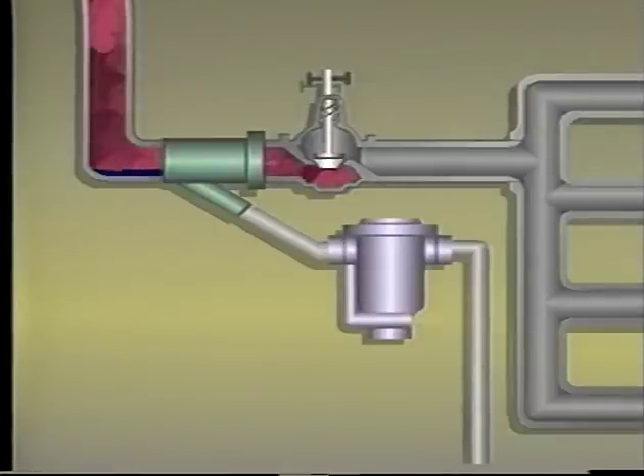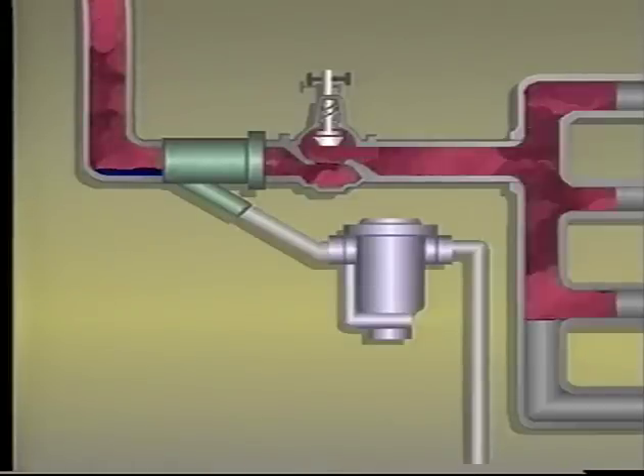The installation of a proper drip leg ahead of control valves will prevent differential shock from occurring when the control valve is opened after a period of closure.